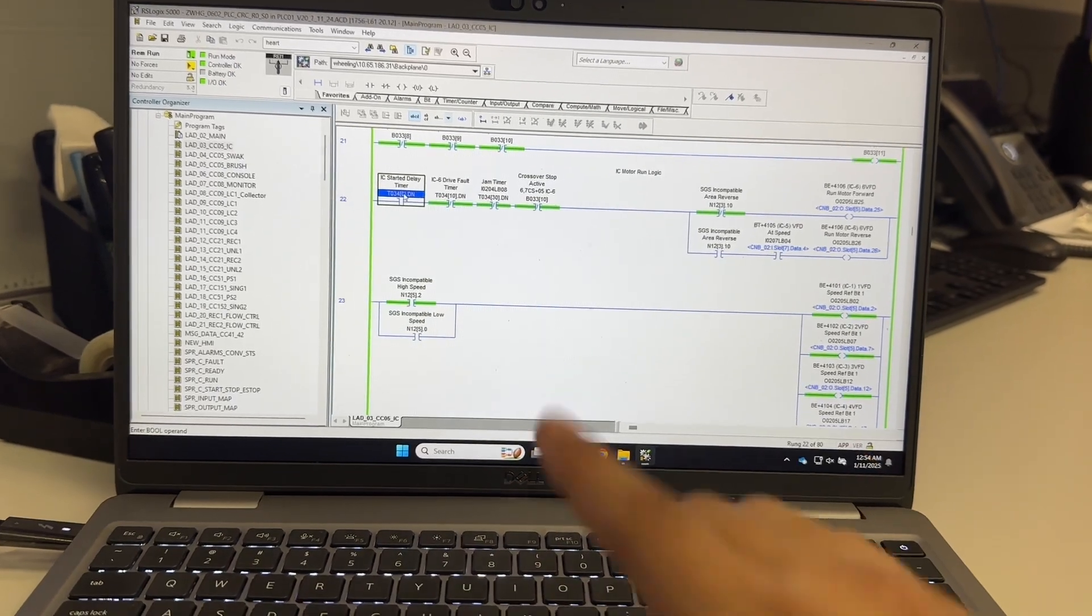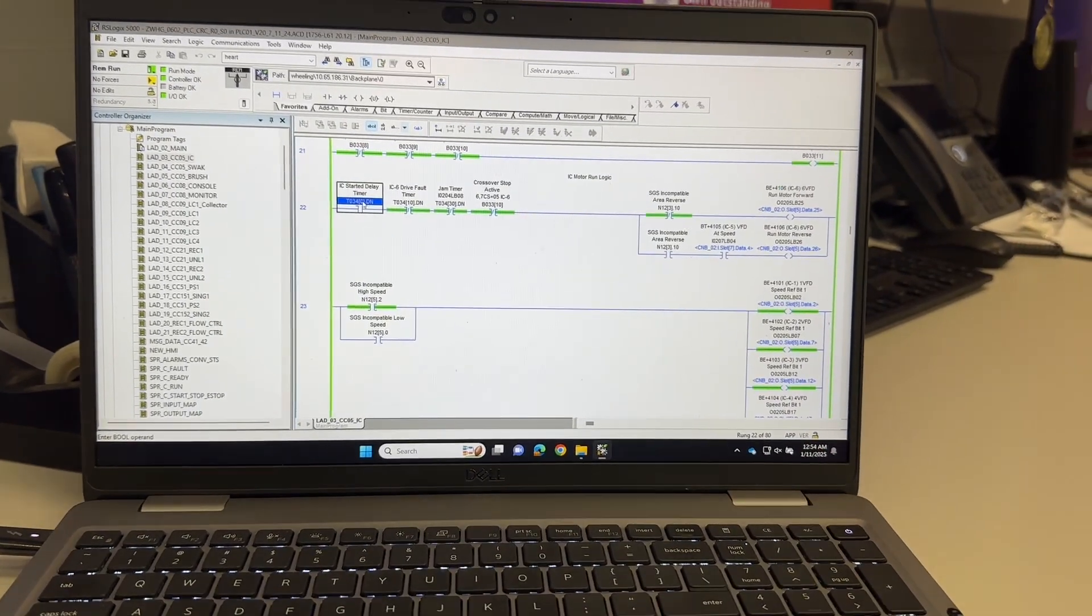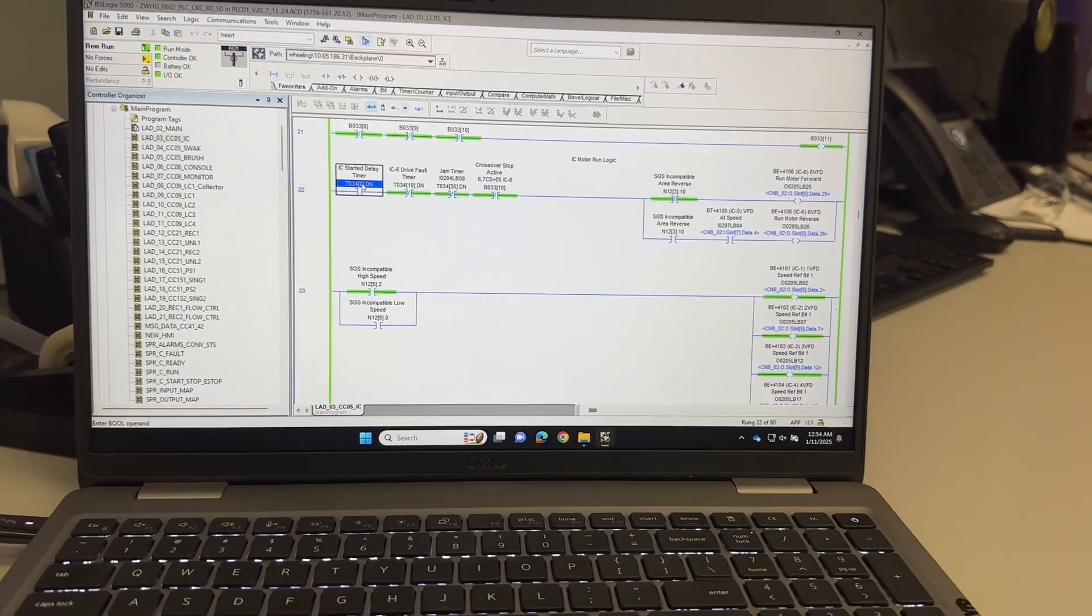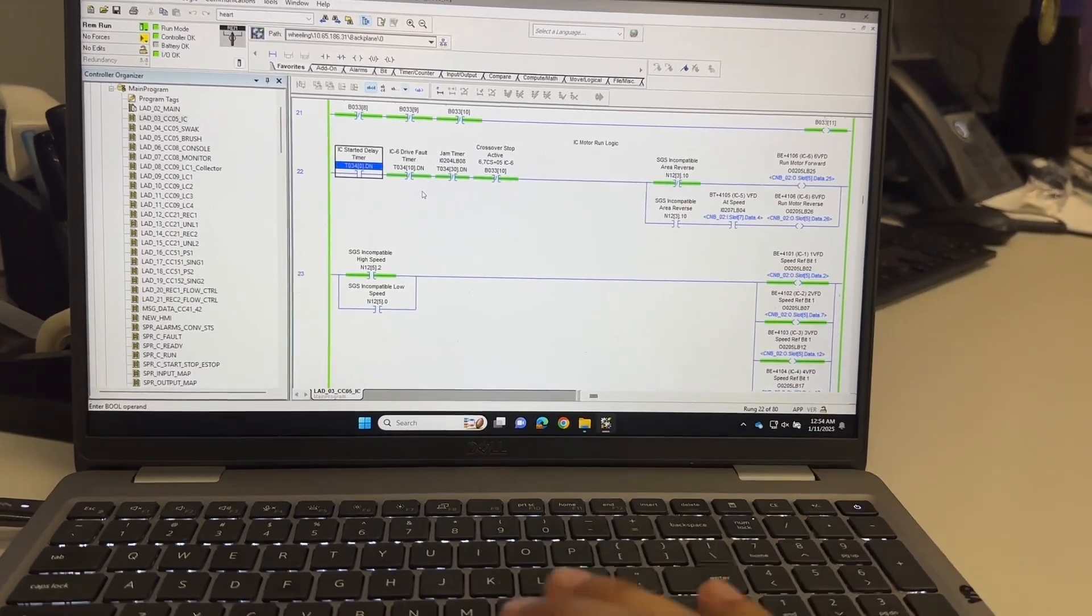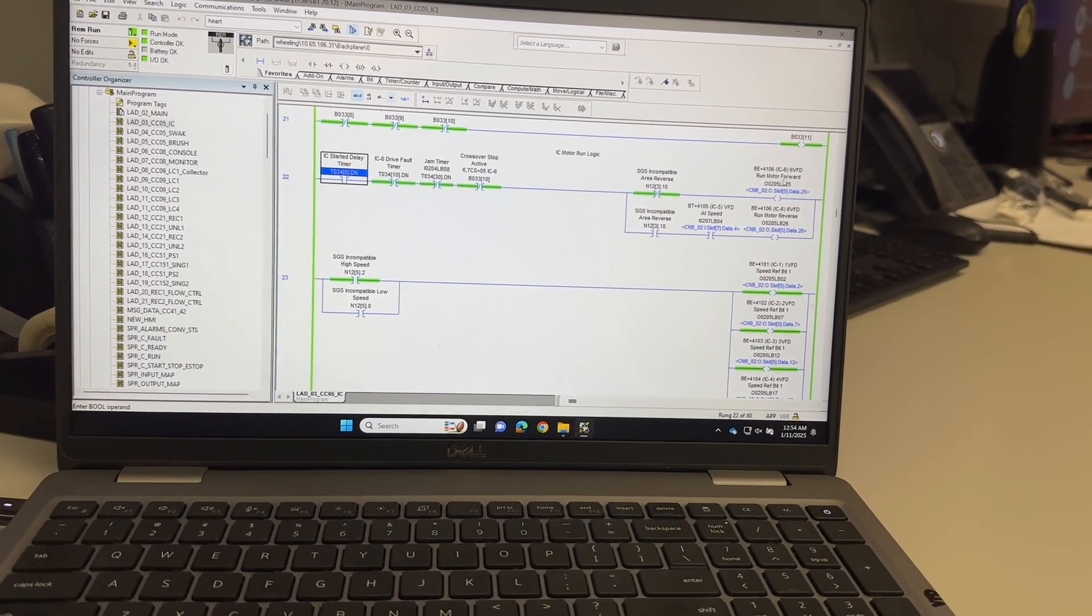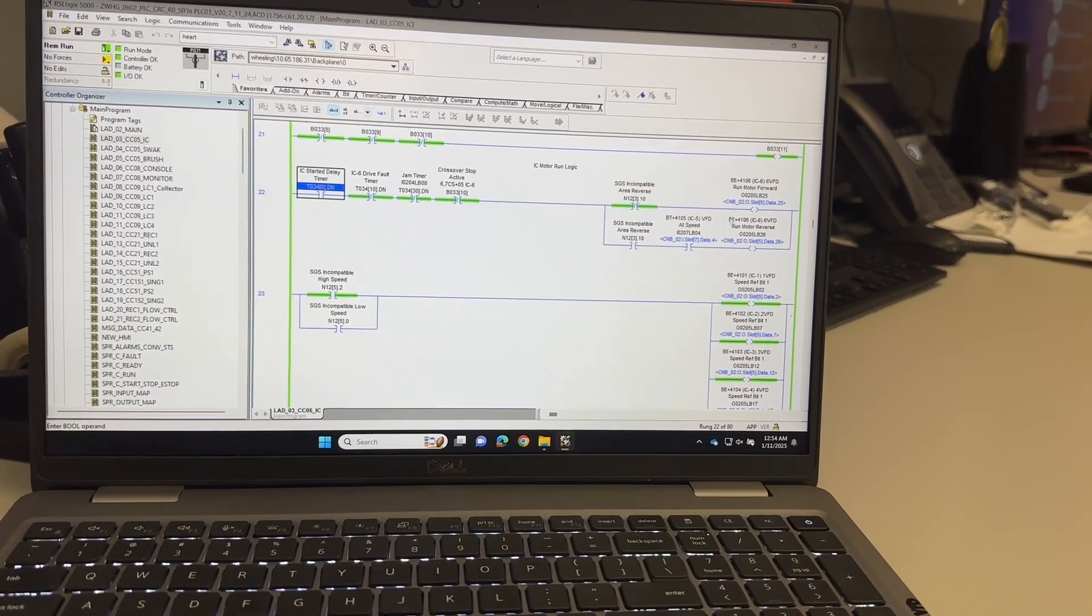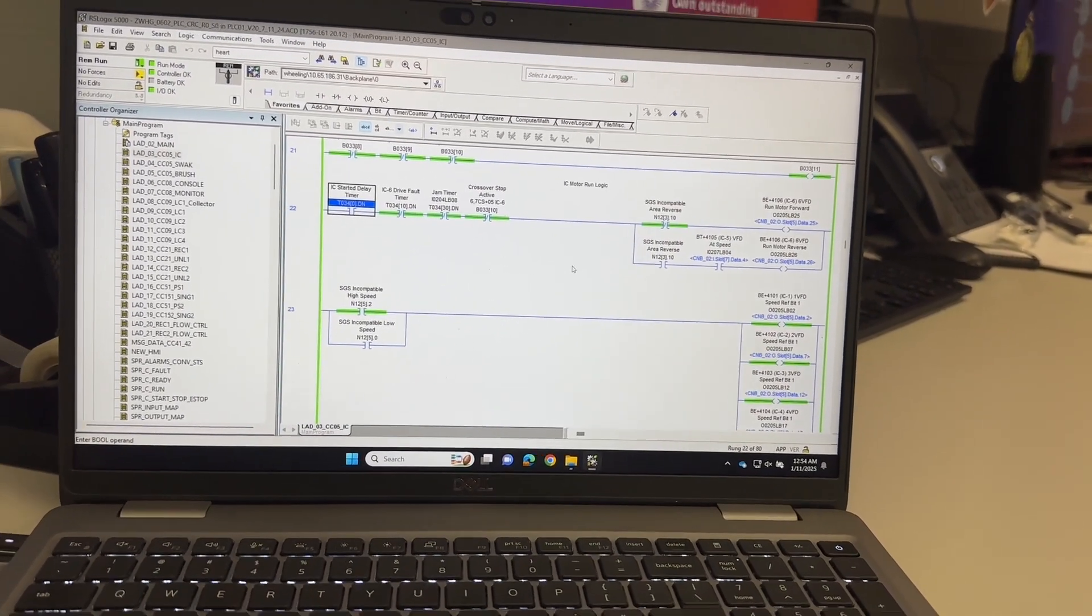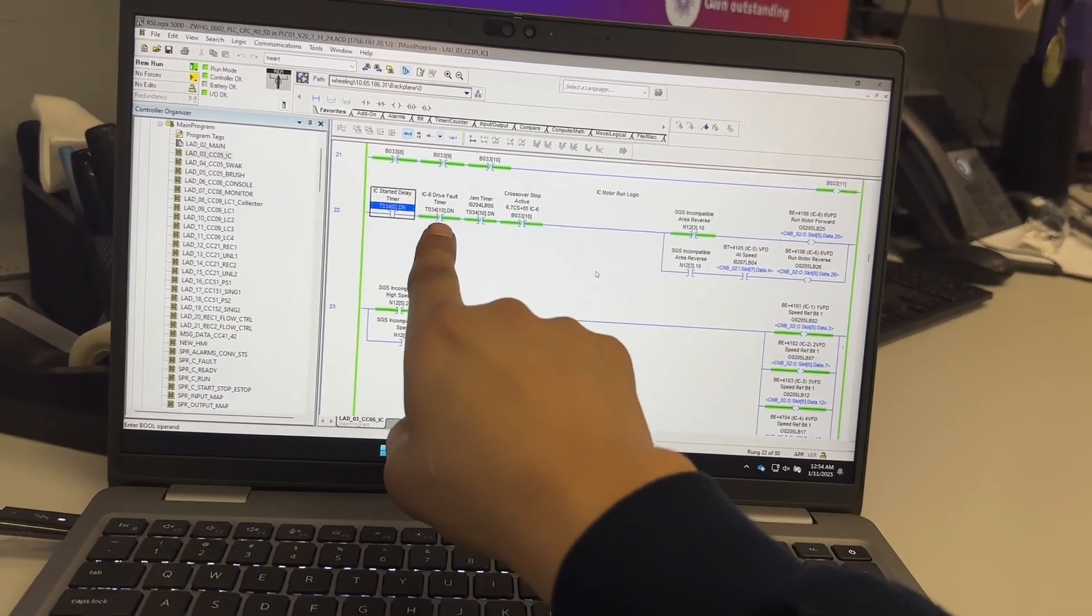For example, I have this machine, this output just run motor forward. It's not running forward because the output is not on. I can see that there's logical continuity through this whole rung except this IC started delay timer. So I want to know why this timer is not running.